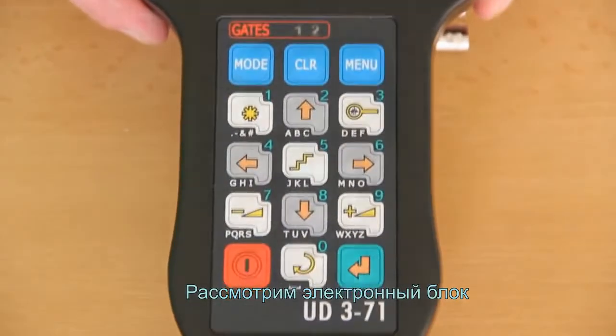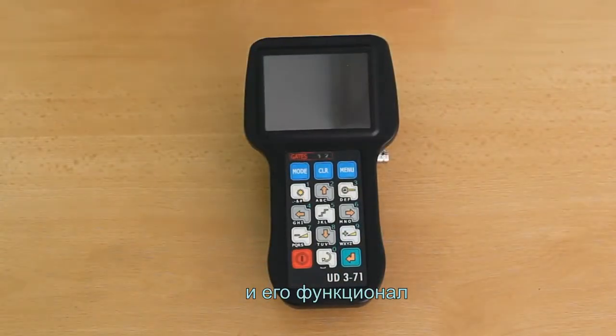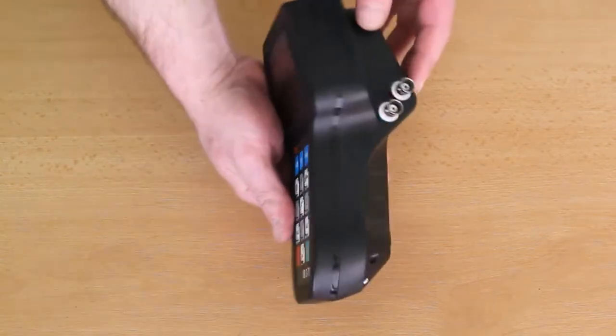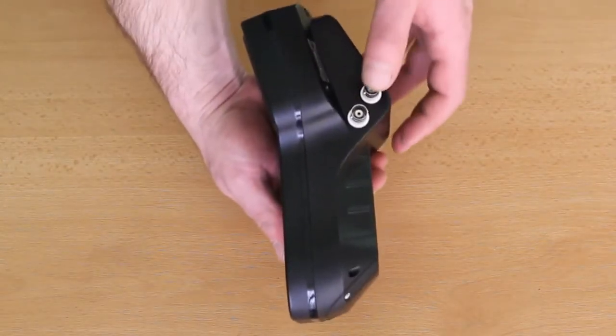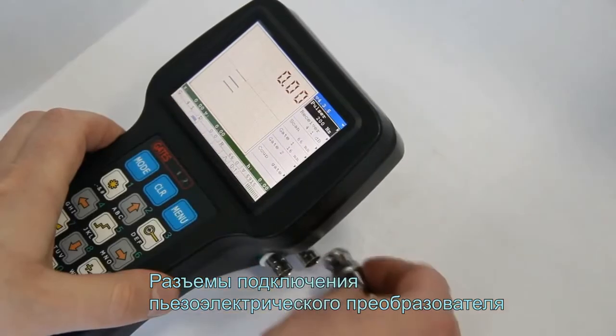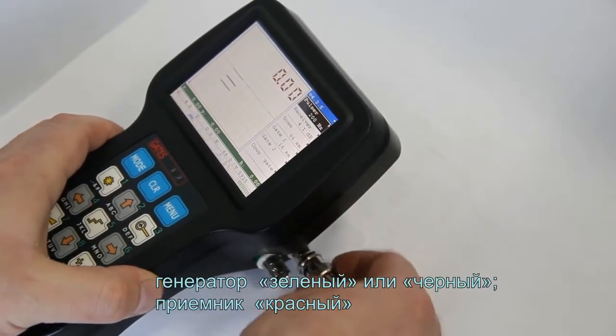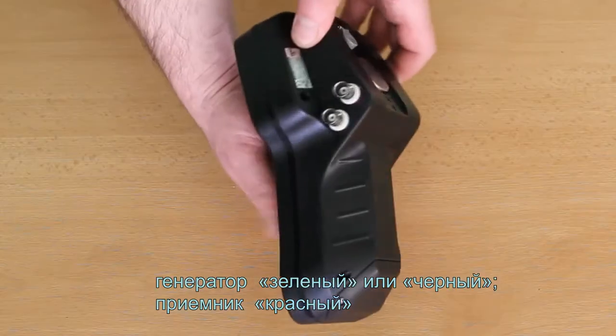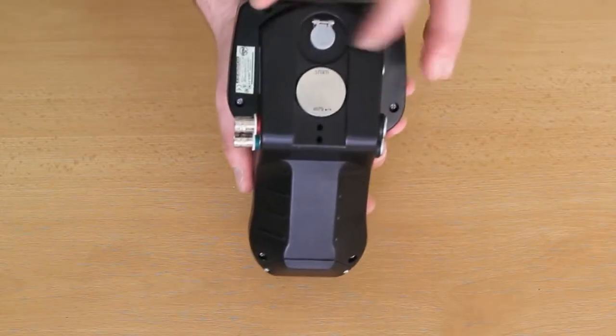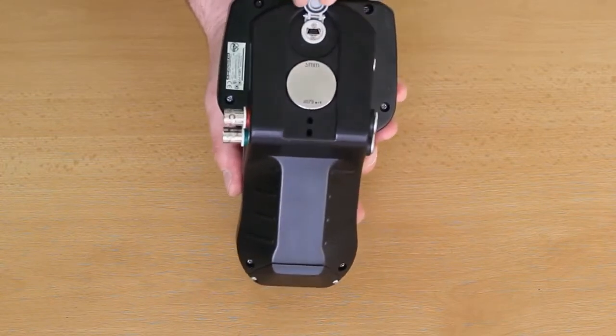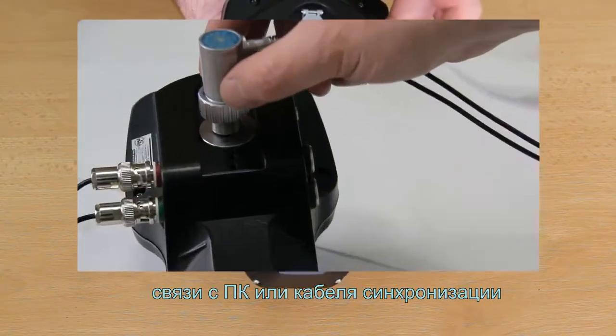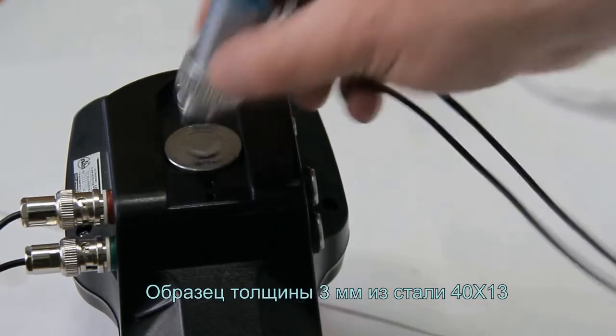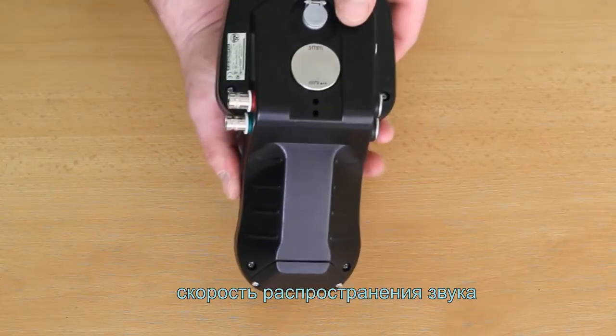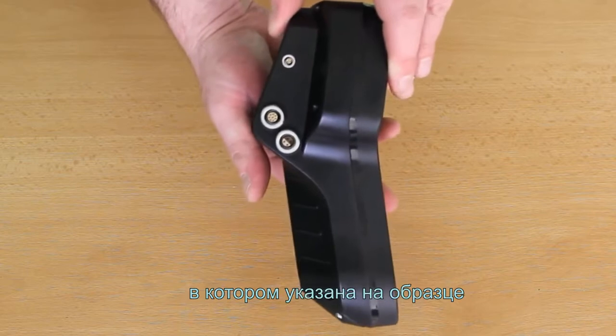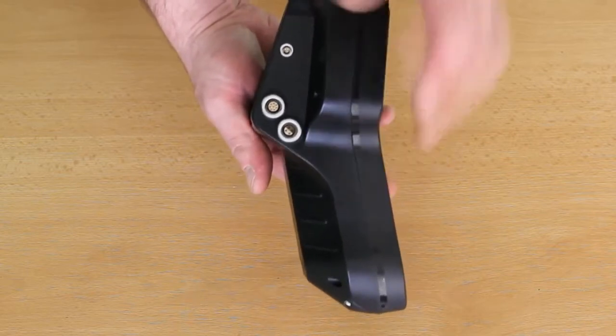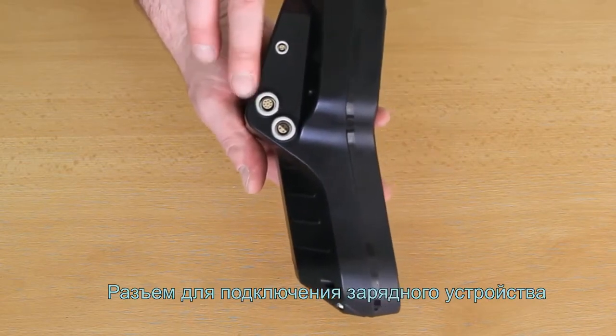Let's see the electronic unit and its functionality. Connectors for piezoelectric transducers connection. Pulser is marked in a green or black color, receiver in a red one. USB connector for connection of the PC communication cable or synchronization cable. 3 mm calibration block, 40H 13 steel, for sound velocity calibration that is specified on the calibration block. Charger connector, encoder connector, headphones connector.